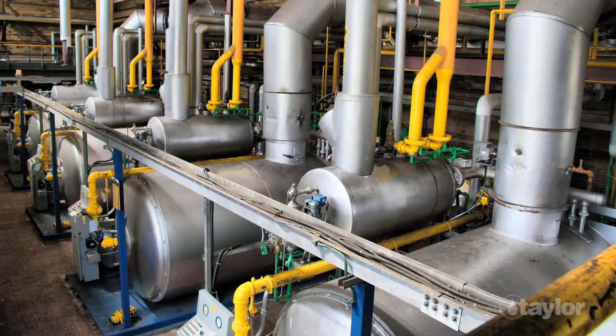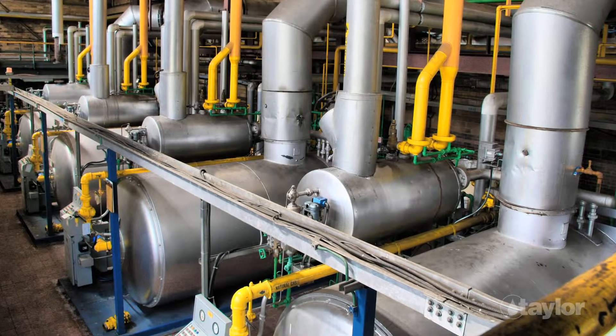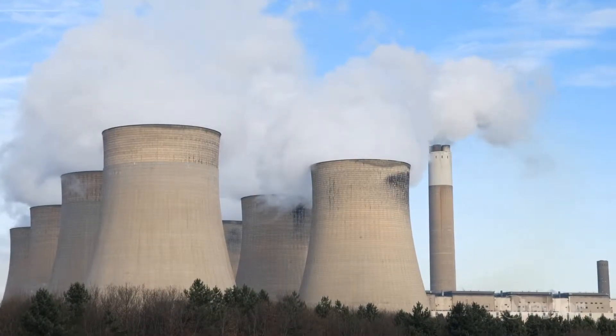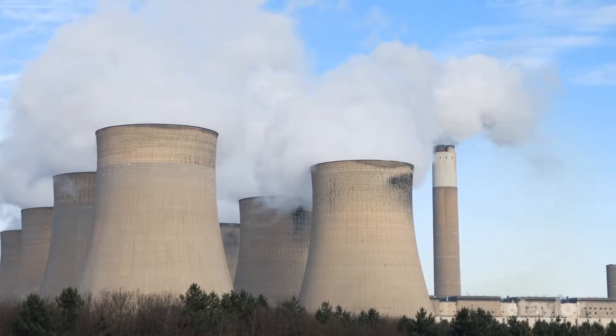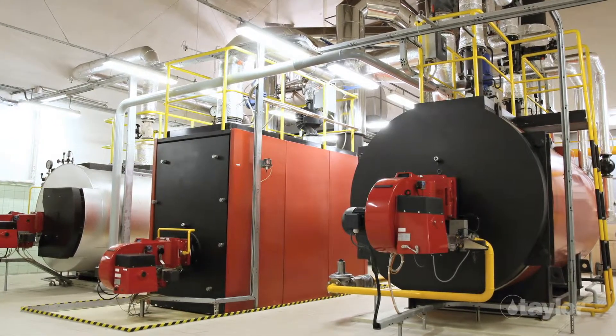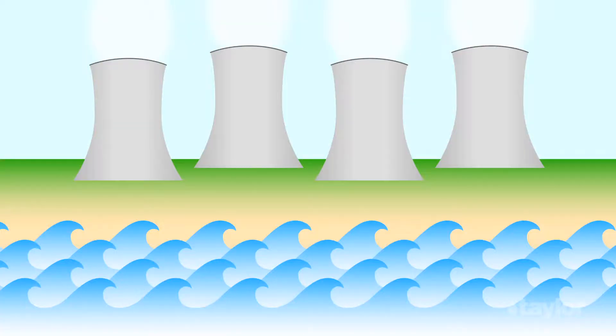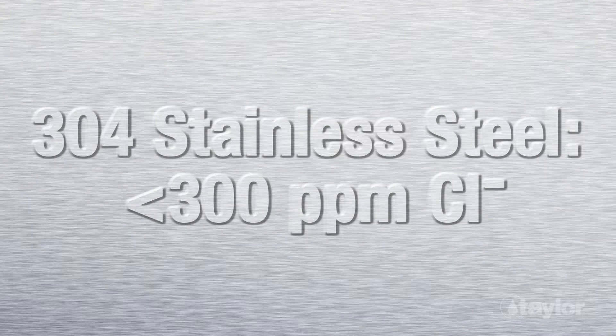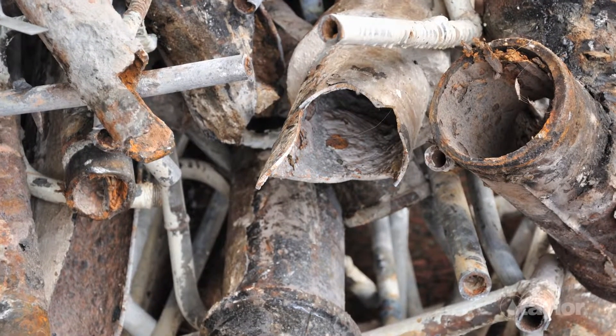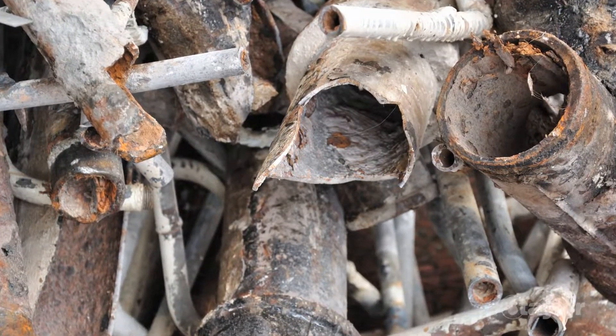Chlorides can enter surface water in many ways: wastewater from industries, agricultural runoff, and road salting, to name just a few. Testing for chlorides is primarily used to control blowdown in boilers and bleed-off in cooling systems. Determining levels of this chemical is also helpful in characterizing boiler feed water and detecting leaks in boiler condensate systems. Chloride is prevalent in seawater, which many industries use to fulfill their cooling water needs. All cooling waters have a recommended maximum chloride level — too high a level can corrode metal pipes and equipment, resulting in shutdowns for repairs and replacement of costly equipment.